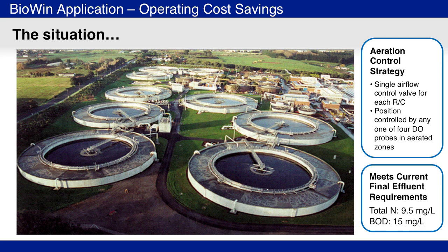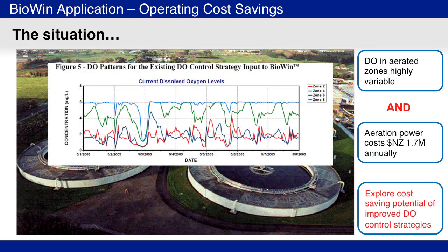The position of this valve was set according to the readings of any one of the four dissolved oxygen probes in the aerated zones of the reactor clarifier. This aeration control strategy resulted in very high dissolved oxygen levels, especially in the last two aerated zones of the reactor clarifiers. This was resulting in excessive power costs at the plant, with aeration power requirements accounting for 40% of the plant's total power consumption.